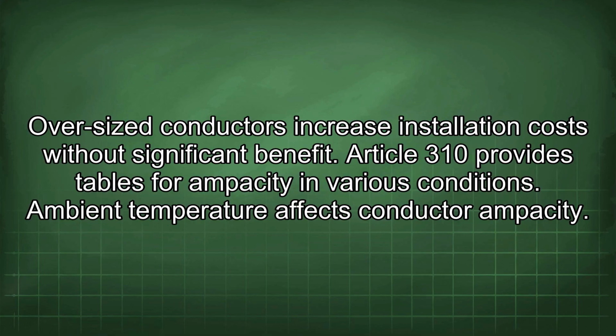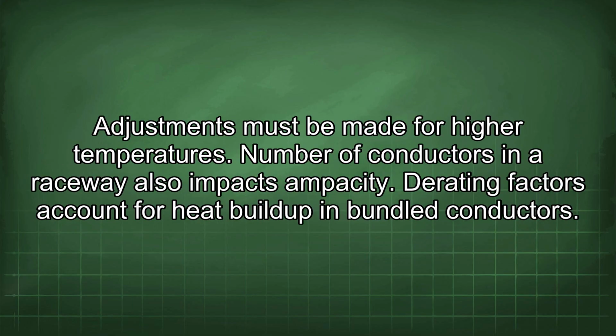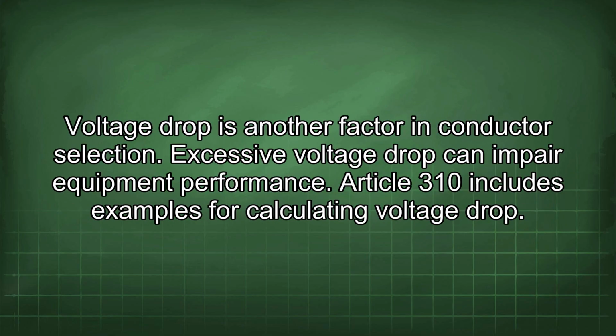Ambient temperature affects conductor ampacity. Adjustments must be made for higher temperatures. The number of conductors in a raceway also impacts ampacity. Derating factors account for heat buildup in bundled conductors. Voltage drop is another factor in conductor selection. Excessive voltage drop can impair equipment performance. Article 310 includes examples for calculating voltage drop.